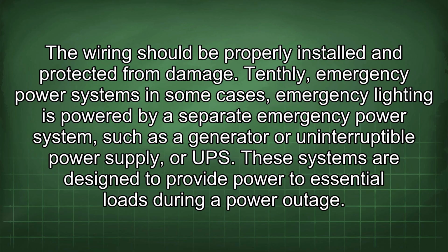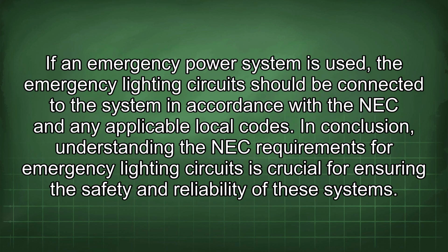Tenthly, emergency power systems. In some cases, emergency lighting is powered by a separate emergency power system, such as a generator or uninterruptible power supply, or UPS. These systems are designed to provide power to essential loads during a power outage. If an emergency power system is used, the emergency lighting circuit should be connected to the system in accordance with the NEC and any applicable local codes.